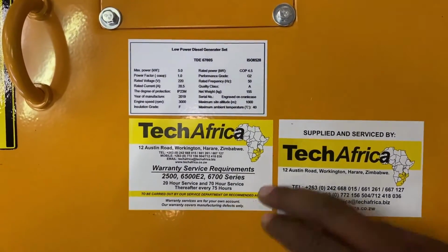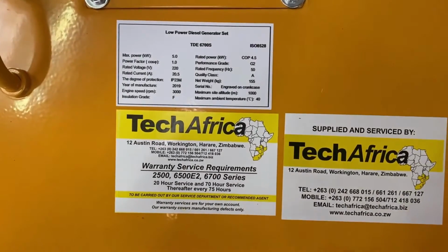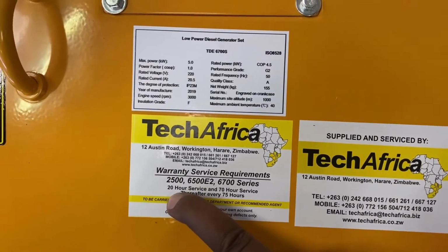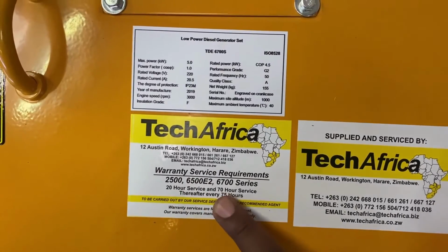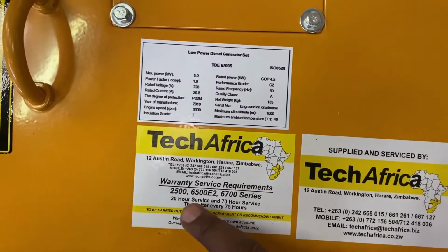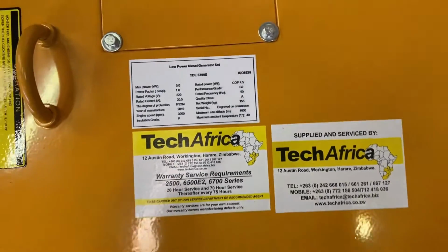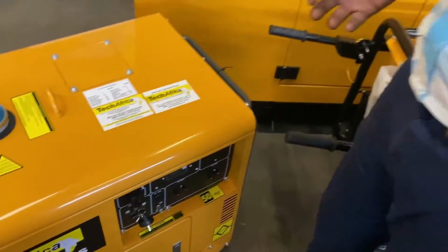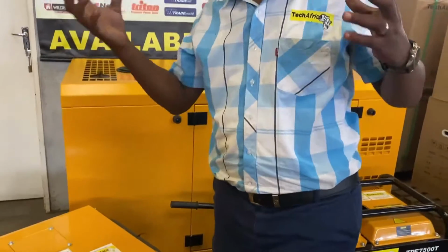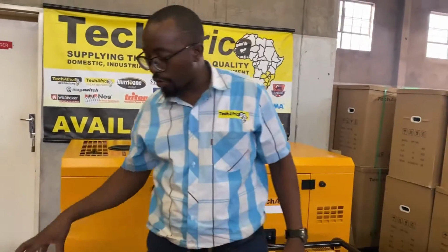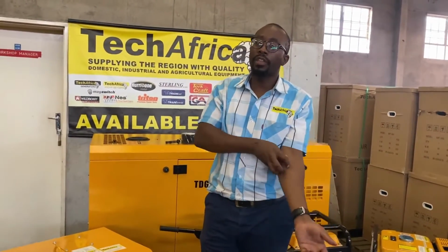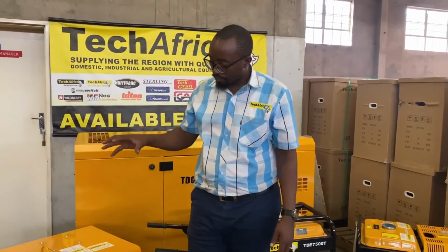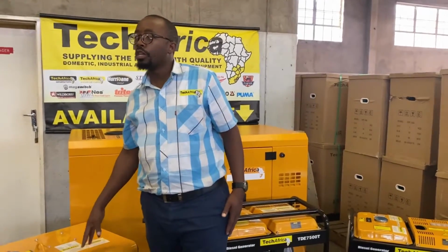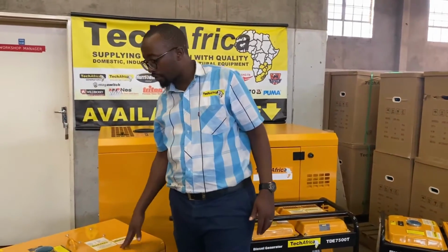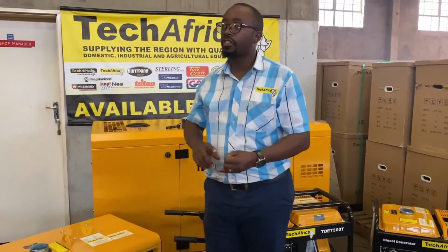Here are the warranty service requirements: your generator has to be serviced at 20 hours, then at 70 hours, and thereafter every 75 hours. At 20 hours, your generator is still brand new and running in, so filings are dropping inside the oil sump. You need to drain the oil and replace it with new oil so the unit has a longer shelf life. So 20 hours is just changing the oil.